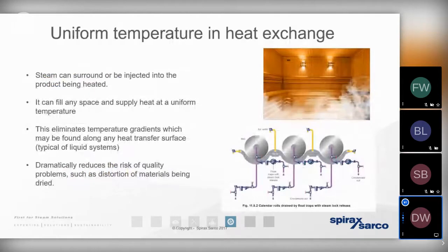So aside from that high energy content that steam has compared to water, we've mentioned in previous presentations, a kilogram of steam's got approximately 50 times more heat energy contained within it than a kilogram of water, especially if that water is only designed to give up a certain amount of temperature at the process. So if we've got a water-to-water heat exchange working on an 11-degree delta T, a kilogram of steam will have 50 times more energy contained within it. So, of course, there's a huge benefit there for our client. They need to generate and distribute far, far less steam. But it also means if we've got more heat energy contained within the steam, the heat exchanger can be smaller compared to a water-to-water heat exchanger.